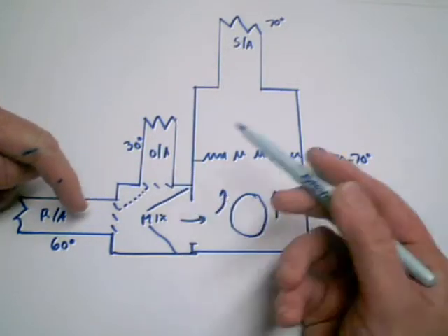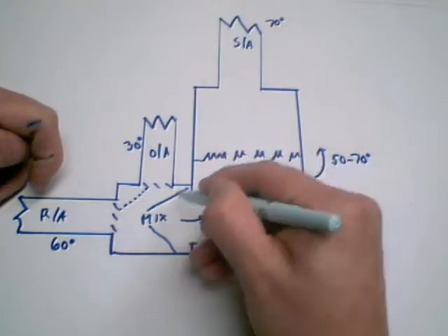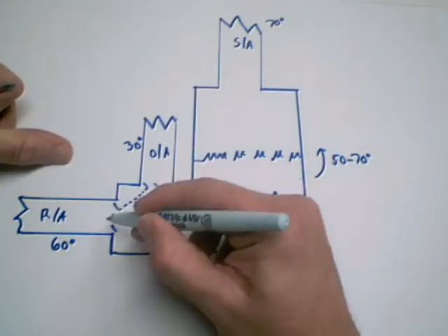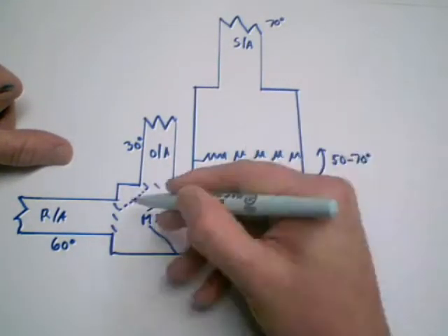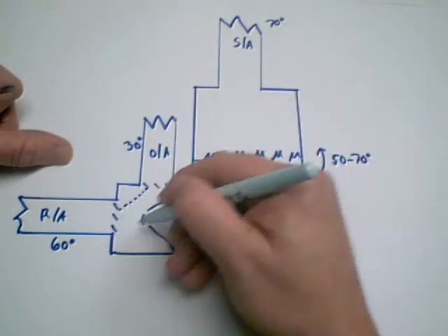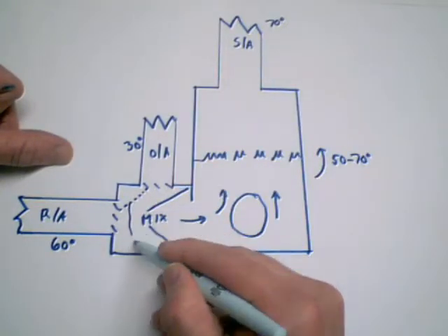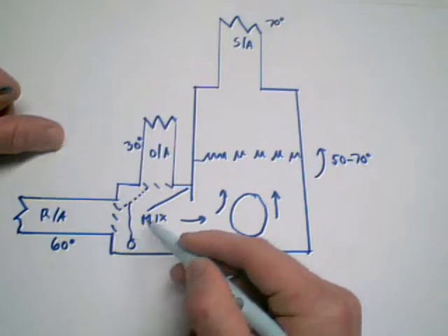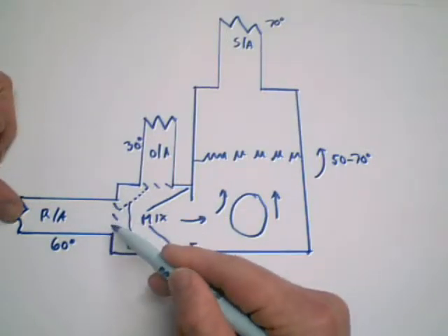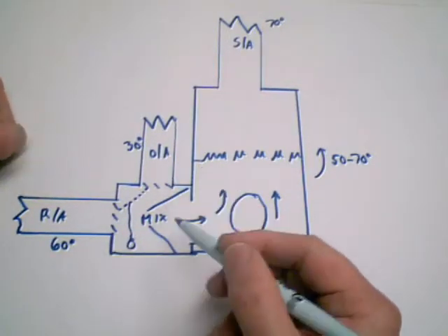If it's 50-50, the ratio would be always so that if one is 30%, then it would be 70%. They're locked together, and then this little linkage comes down here to a motor, and that motor turns it so we can have anywhere from 100% return air to 100% outside air.